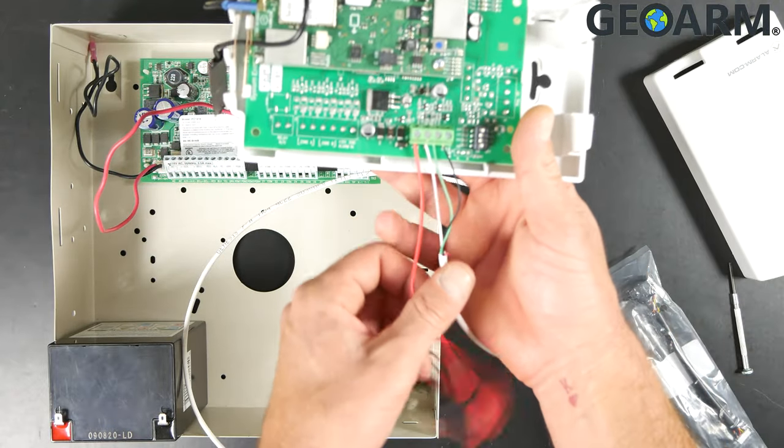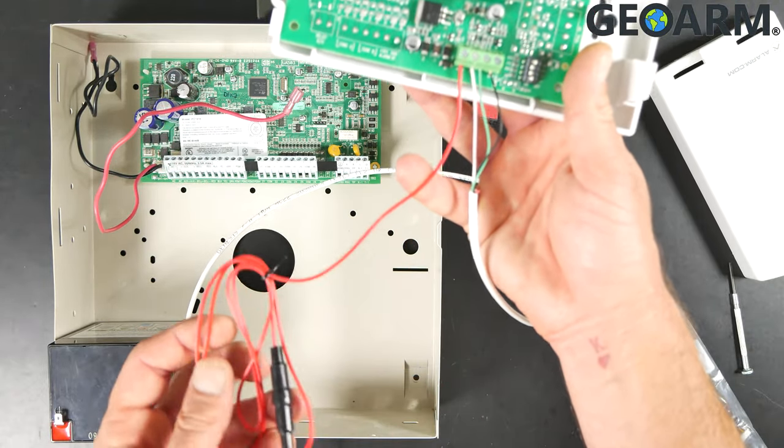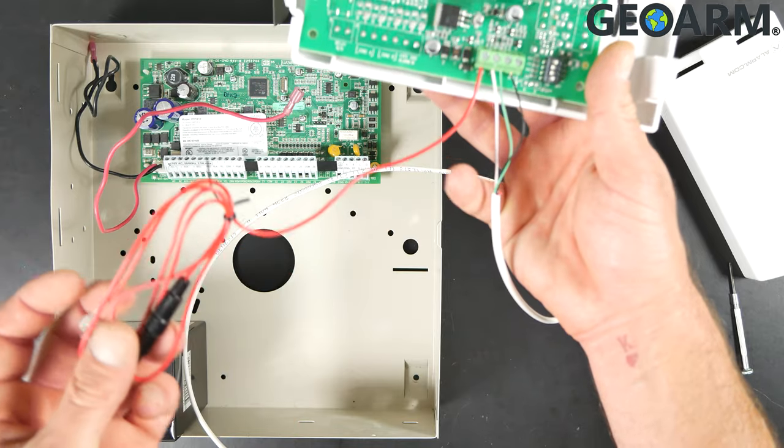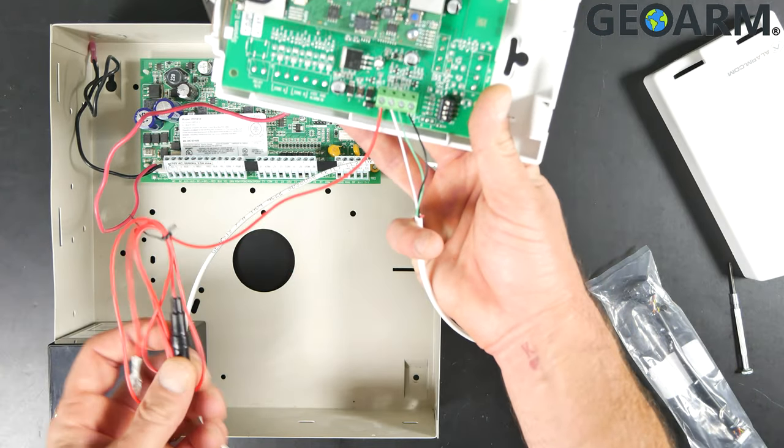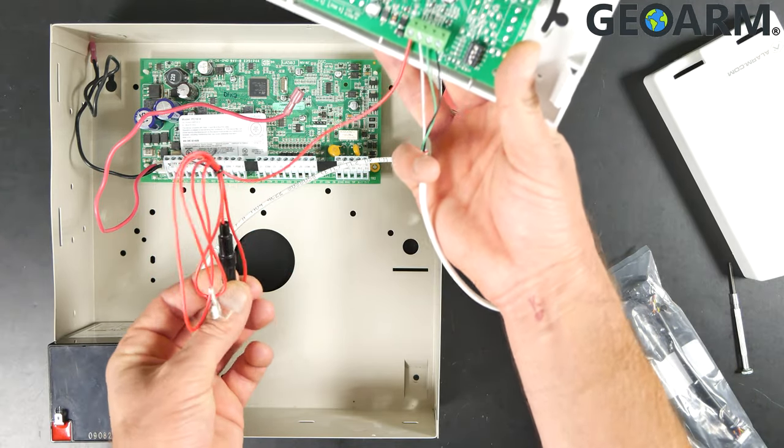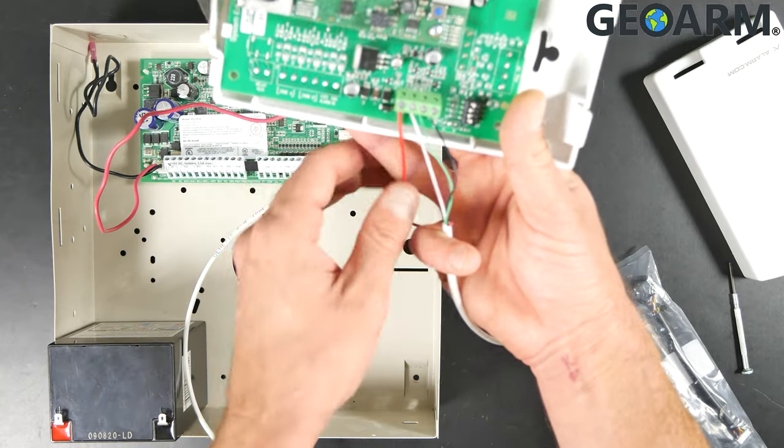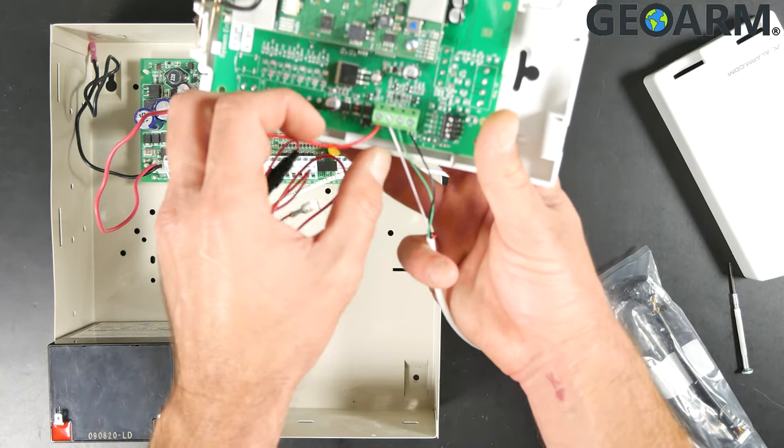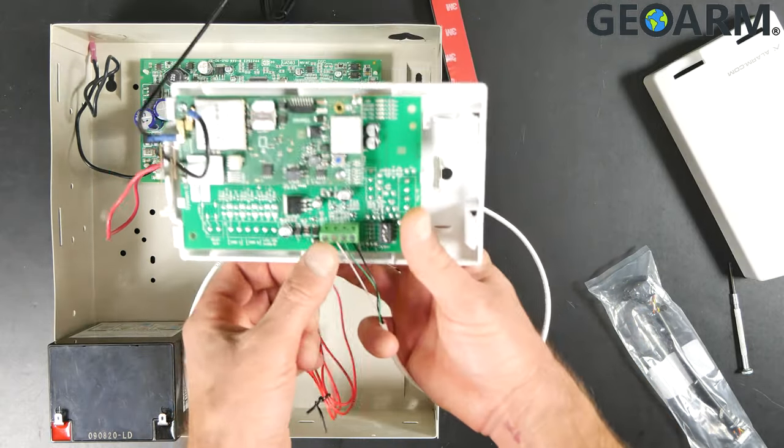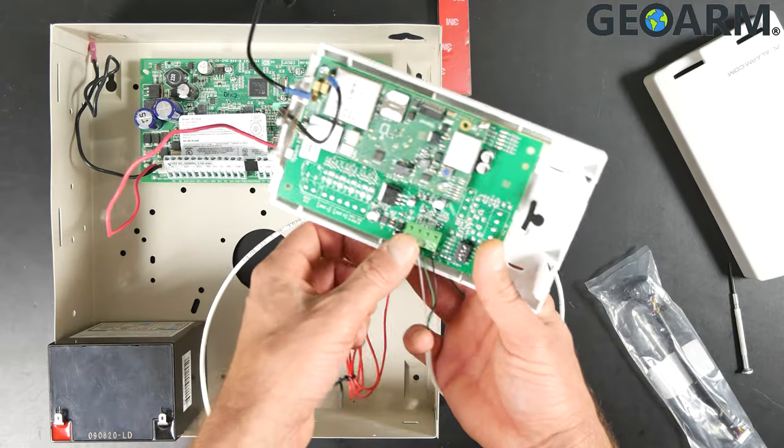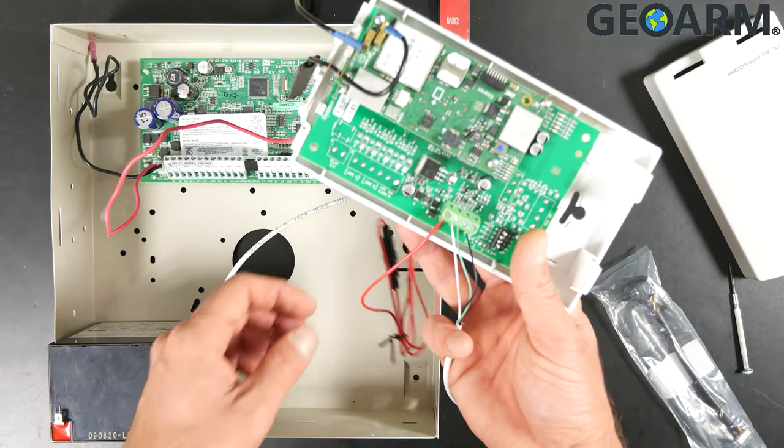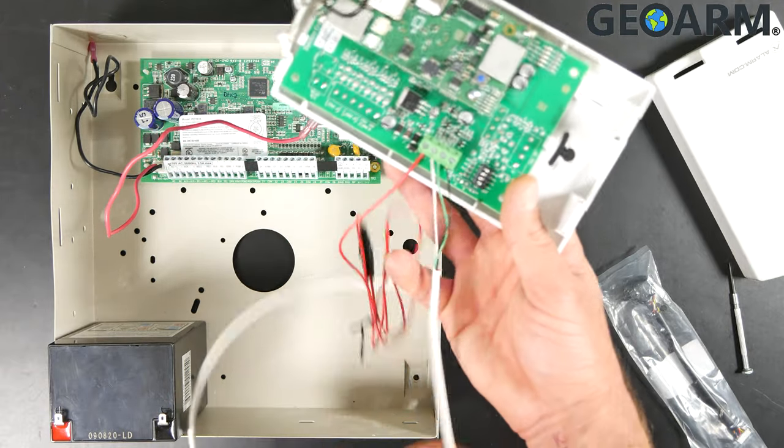Once you look inside here, you'll see that I've already pre-wired this. This is the wire that'll be coming with the ADC SEM unit, which has a little fuse attached to it. This wire you're going to wire into what's called plus 12V. It's on this very far left hand side terminal.